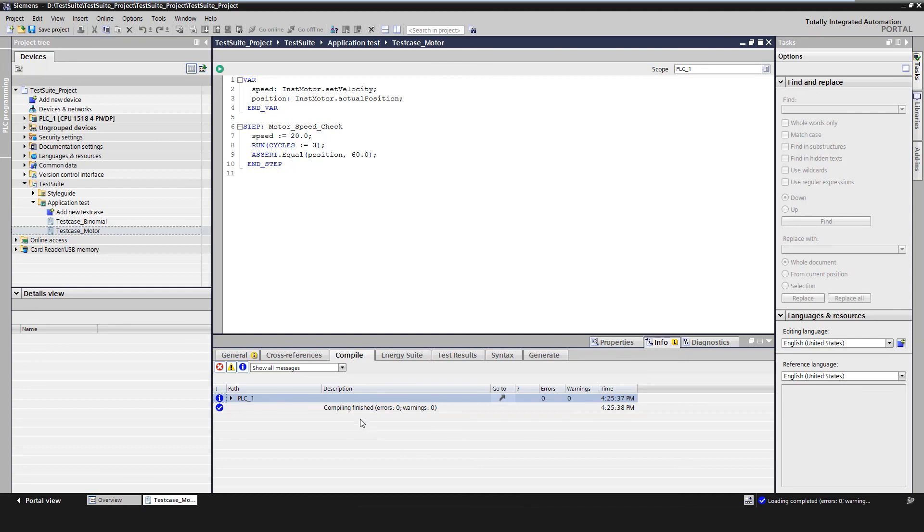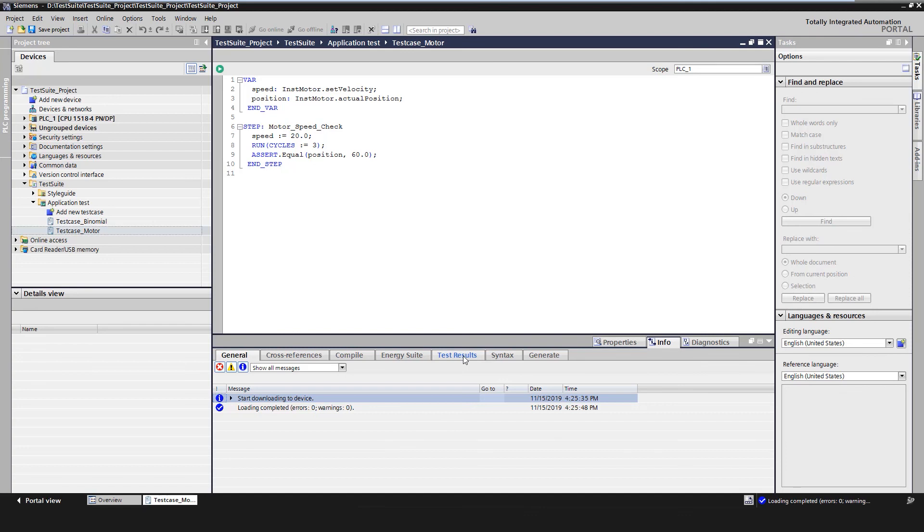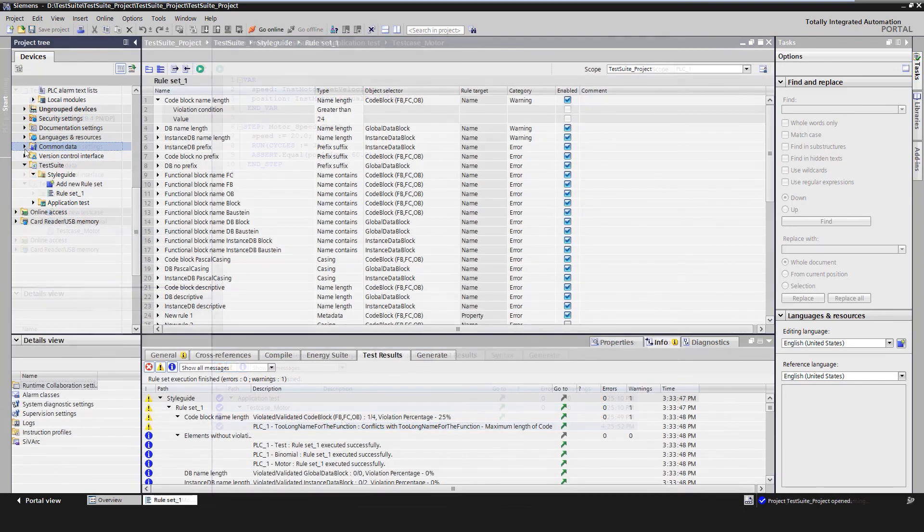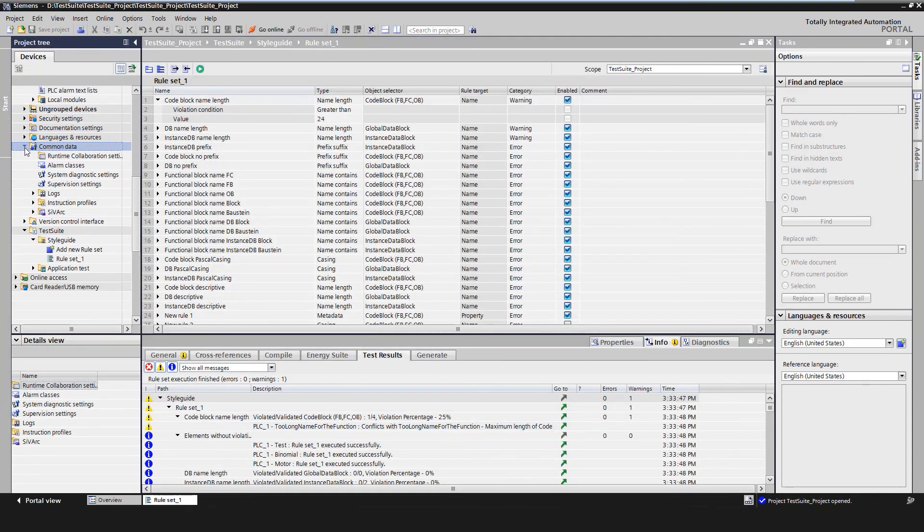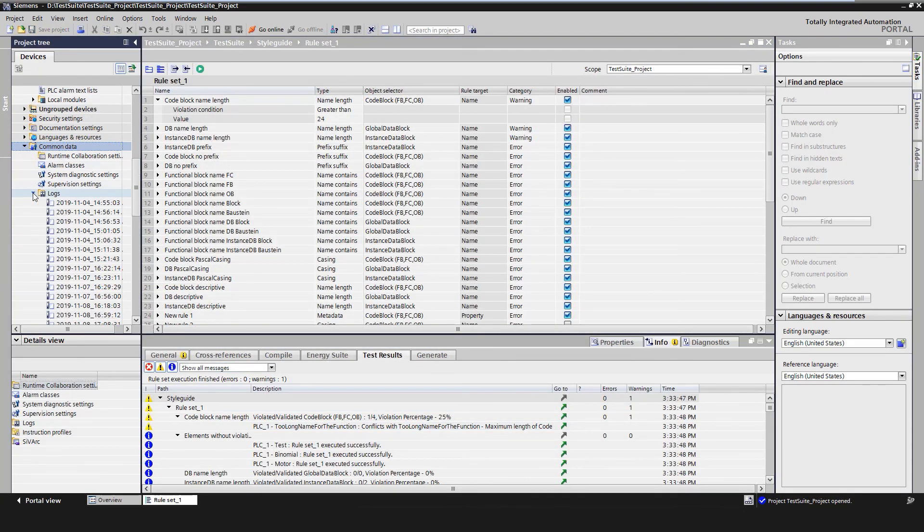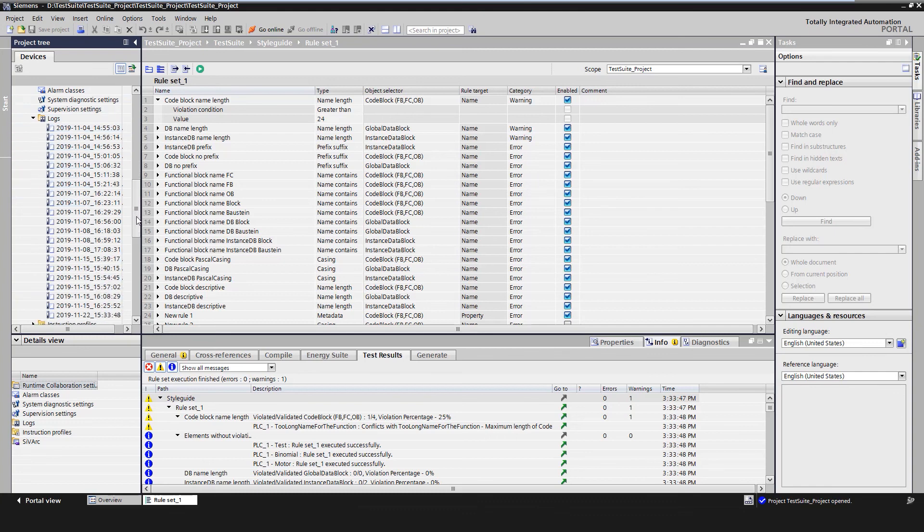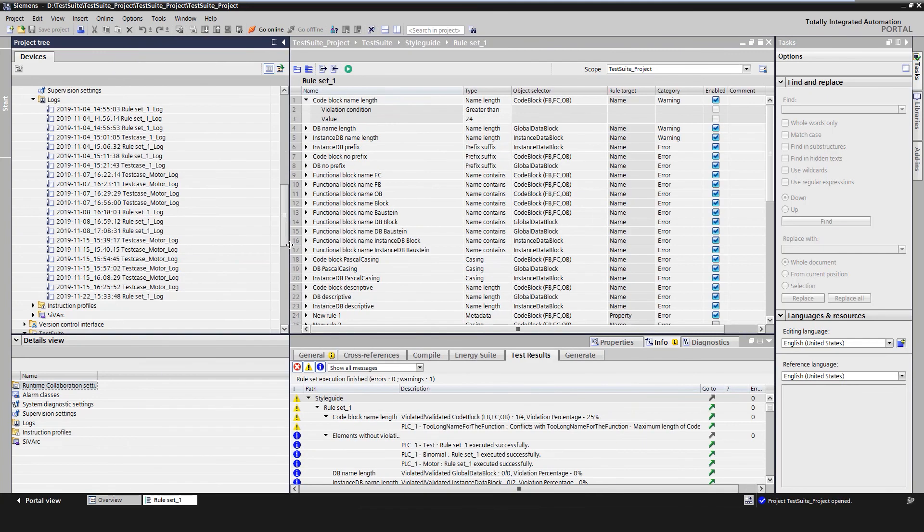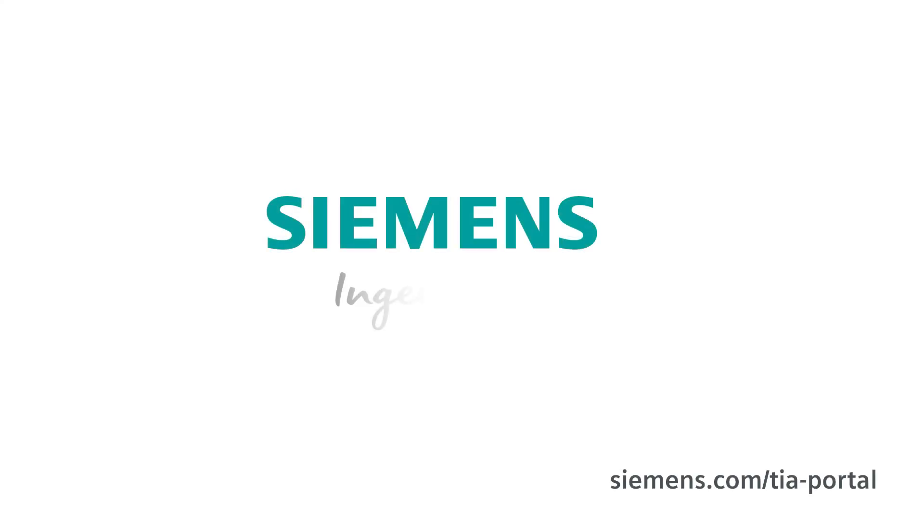Second, the download result in the tab General. Here we can check if a specific project is downloaded to a PLCSIM Advanced instance. And third, the test result in the Test Results tab. All test results are stored in the TIA Portal project under Common Data in Logs. This documents the test execution in the project. This makes it possible, for example, to track when an error first occurred. Siemens, Ingenuity for Life.